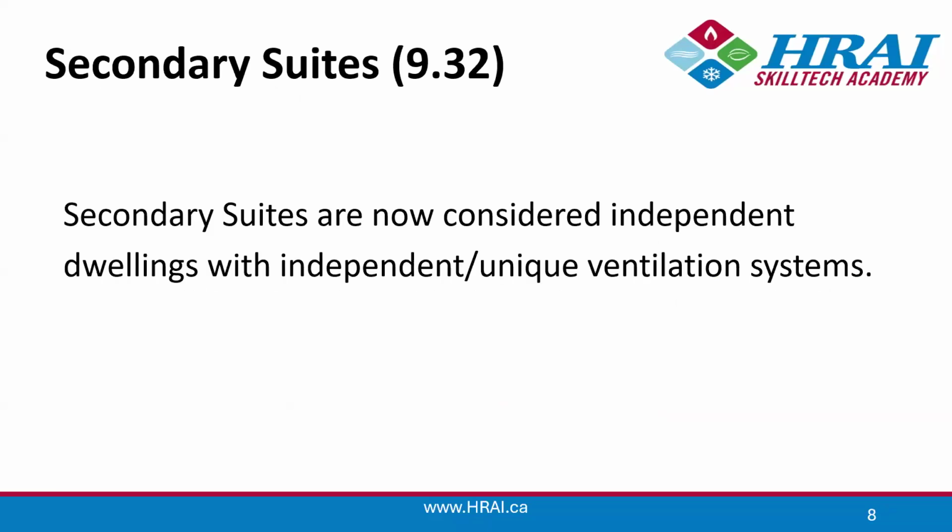Another big change is secondary suites. Secondary suites had been included in the OBC 2012, and that was more or less to try to drive some cohesion or some ability for people to have secondary suites and combine HVAC systems. That's no longer a thing, so they must have independent, unique ventilation systems, and they're treated as completely independent dwelling units.